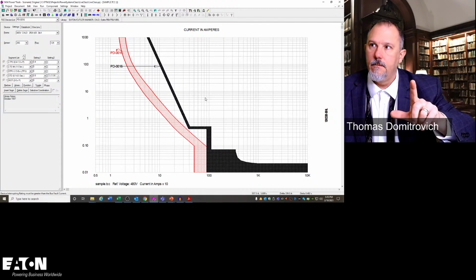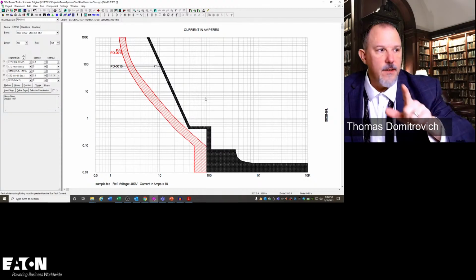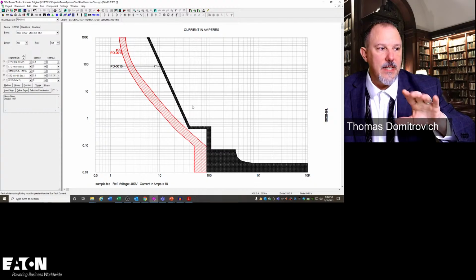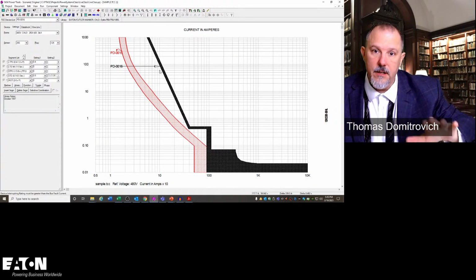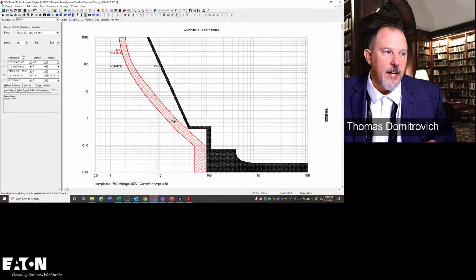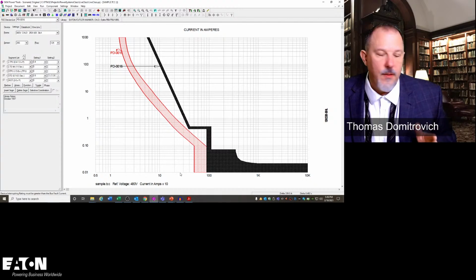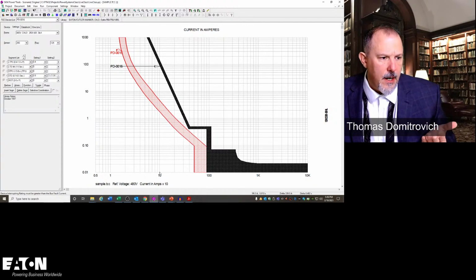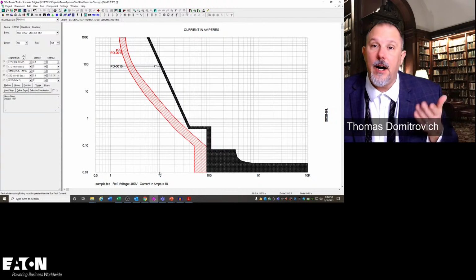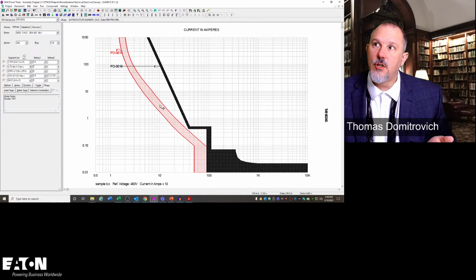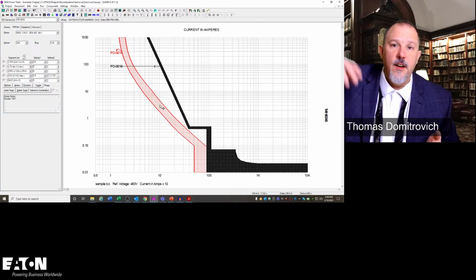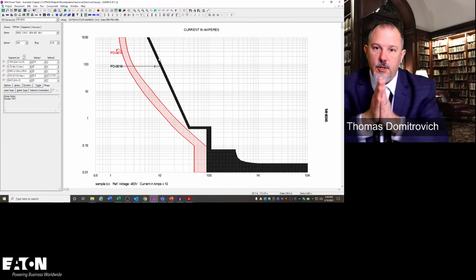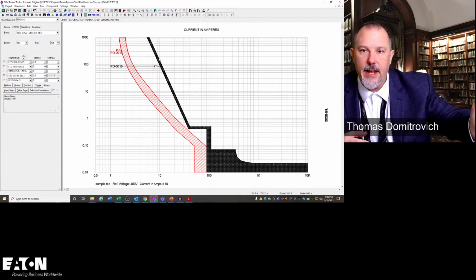So the act of selective coordination is basically finding the recipe for this region, the overload region, the short time delay region, the long time pickup region, so that I have separation of my curves. So I know for any current in the overload, say if I have 99.3 amps, 100 amps, I know that this breaker downstream, this red breaker, is going to trip. And the upstream breaker is going to hold its contacts closed at 100 amps.